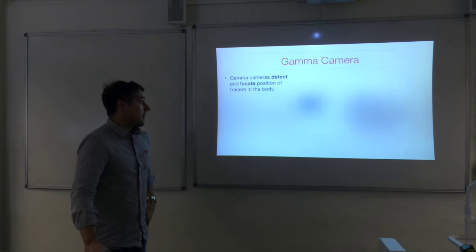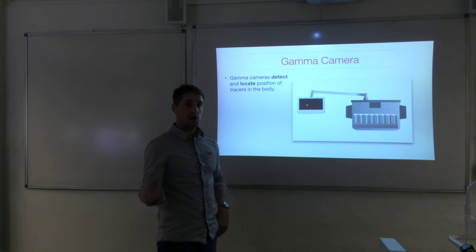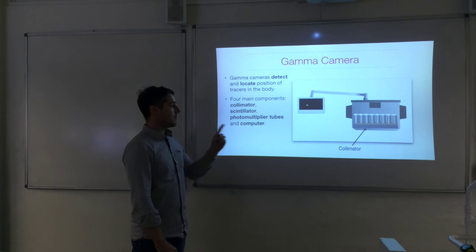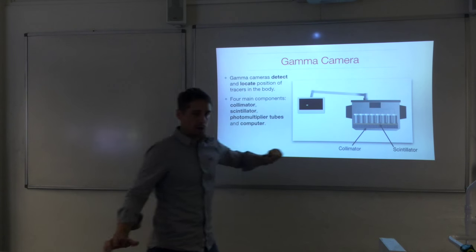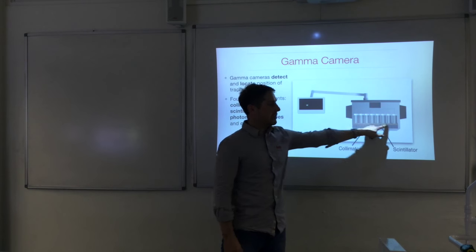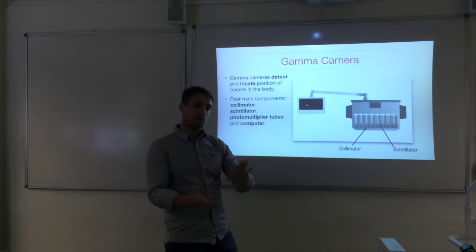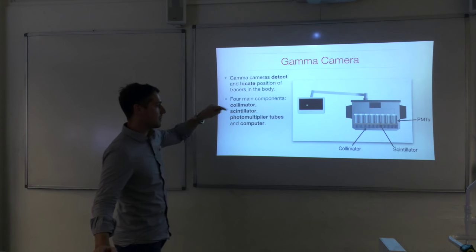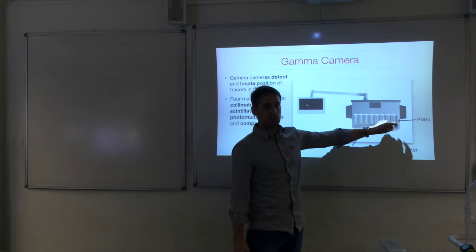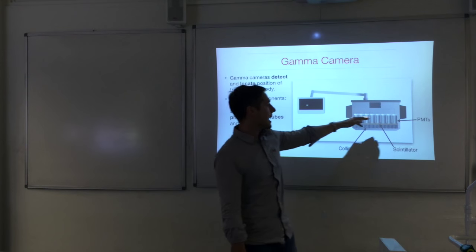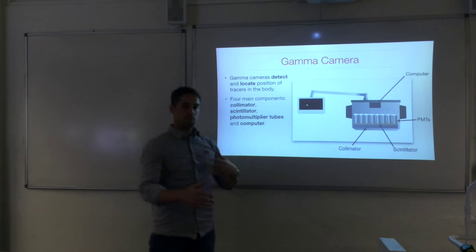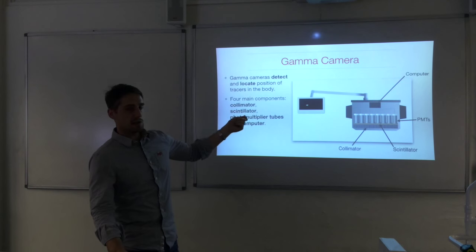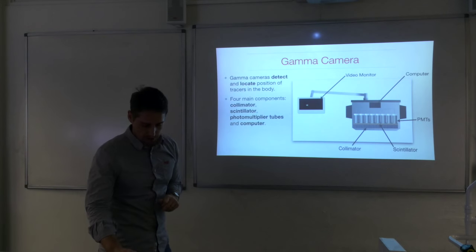The gamma camera is used to detect and locate where the tracer is in the body. There are four main components: the collimator — an array of lead tubes at the bottom; the scintillator material, which behaves like the image intensifying screens we've seen with x-rays; the photomultiplier tubes (PMTs), which convert flashes of light into electronic pulses that are amplified; and the computer, which processes all the information and displays an image on the video monitor for the radiologist.